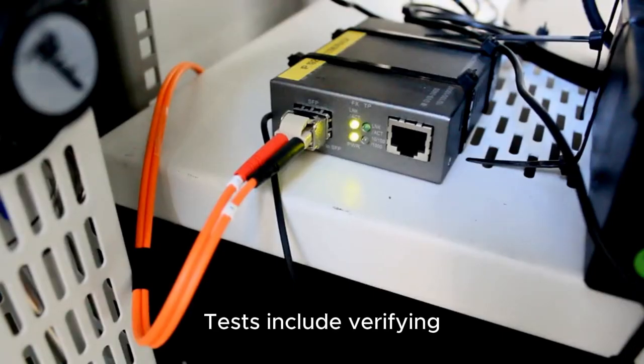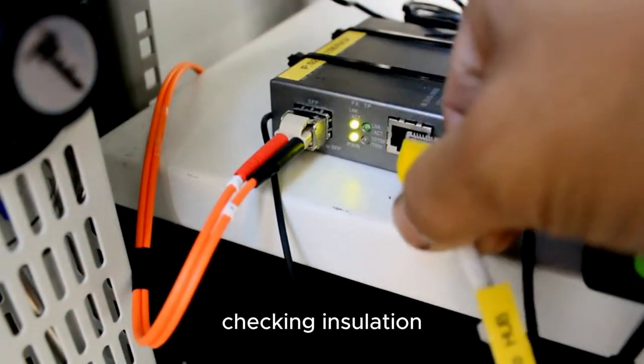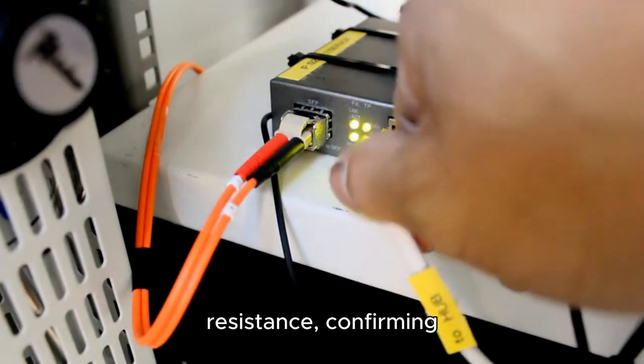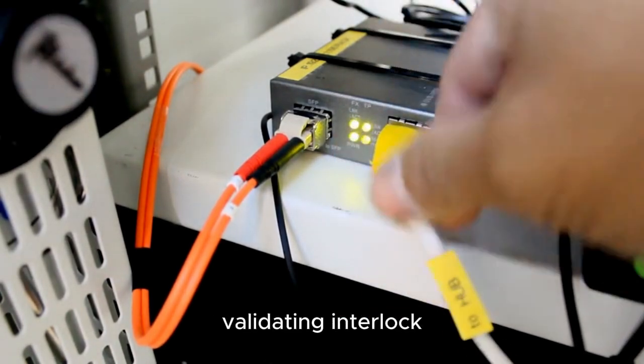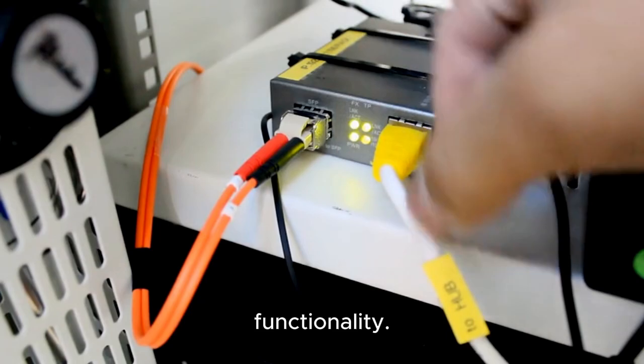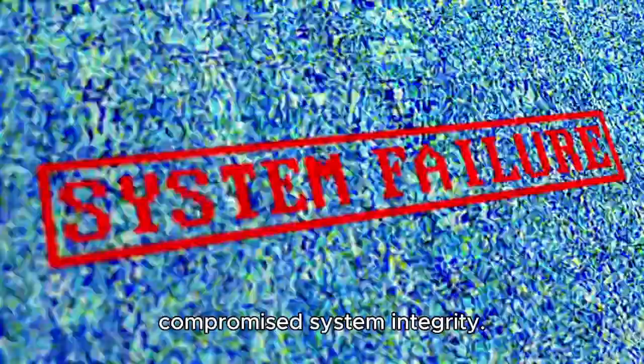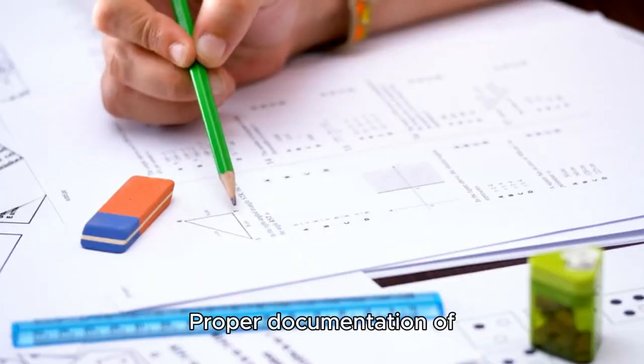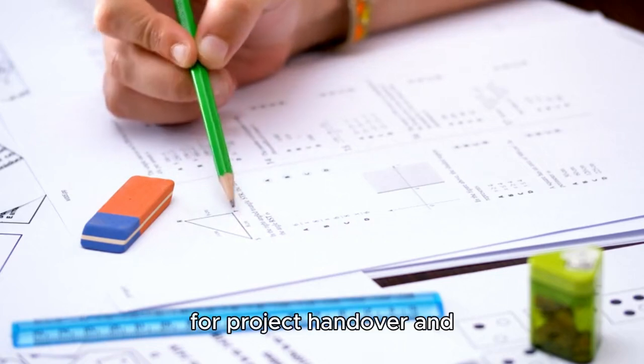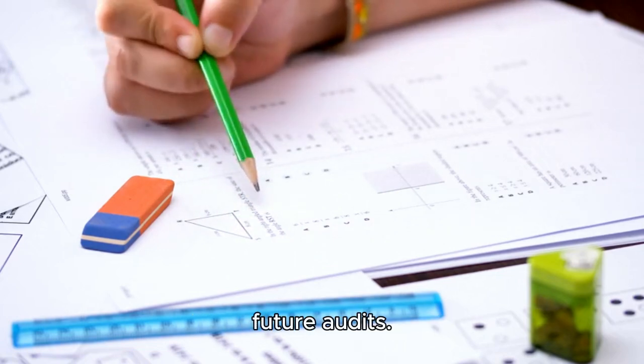Tests include verifying wiring and terminations, checking insulation resistance, confirming control circuits, and validating interlock functionality. SAT also verifies that any changes made during or after FAT haven't compromised system integrity. Proper documentation of SAT results is essential for project handover and future audits.